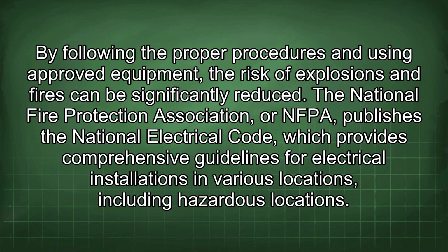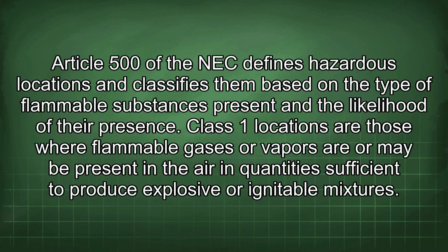The National Fire Protection Association, or NFPA, publishes the National Electrical Code, which provides comprehensive guidelines for electrical installations in various locations, including hazardous locations. Article 500 of the NEC defines hazardous locations and classifies them based on the type of flammable substances present and the likelihood of their presence. Class 1 locations are those where flammable gases or vapors are or may be present in the air in quantities sufficient to produce explosive or ignitable mixtures.